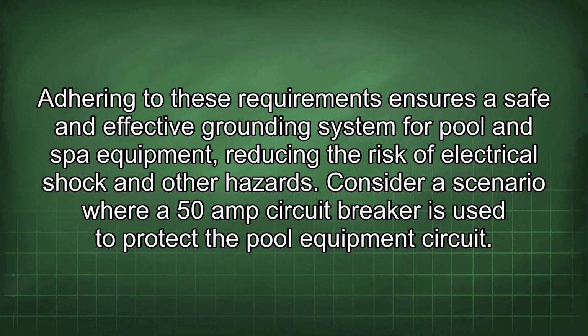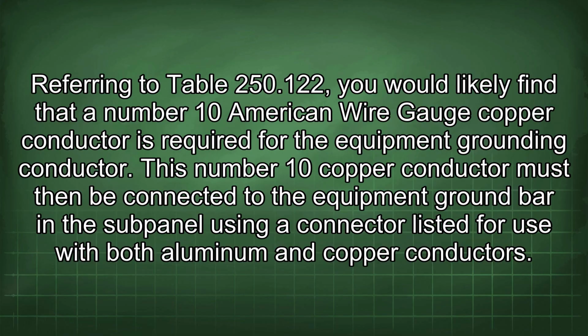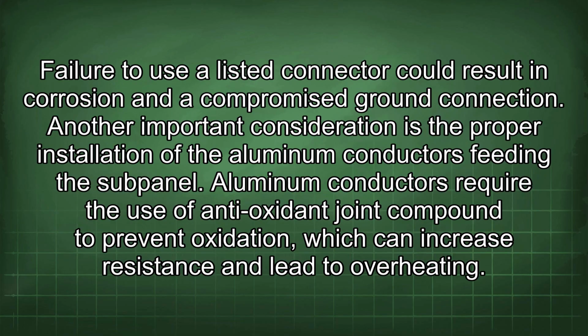Consider a scenario where a 50 amp circuit breaker is used to protect the pool equipment circuit. Referring to Table 250.122, you would likely find that a number 10 American wire gauge copper conductor is required for the equipment grounding conductor. This number 10 copper conductor must then be connected to the equipment ground bar in the subpanel using a connector listed for use with both aluminum and copper conductors. Failure to use a listed connector could result in corrosion and a compromised ground connection.